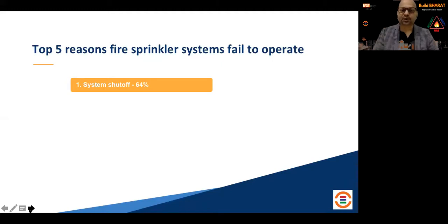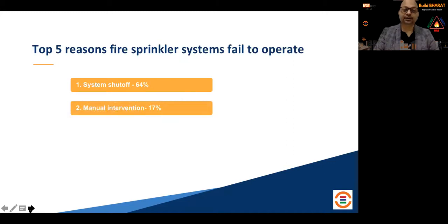So the requirement is that if there's any butterfly valve used on the sprinkler riser, it must be connected to the fire alarm panel with a tamper switch. How many installations have got a tamper switch connected? Now there are valves with built-in tamper switches available, so there's no constraint. But how many people are aware of this? How many people are actually doing it?